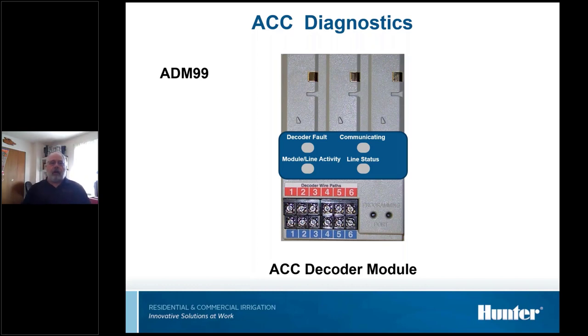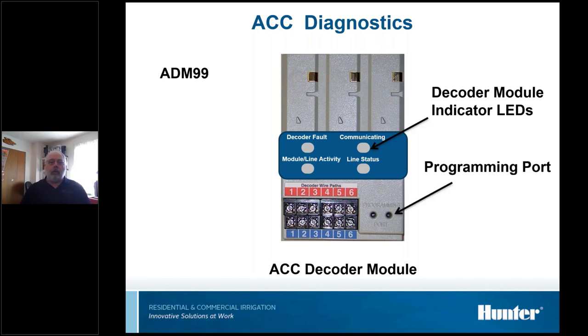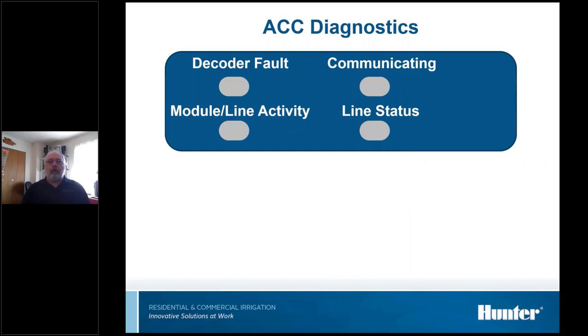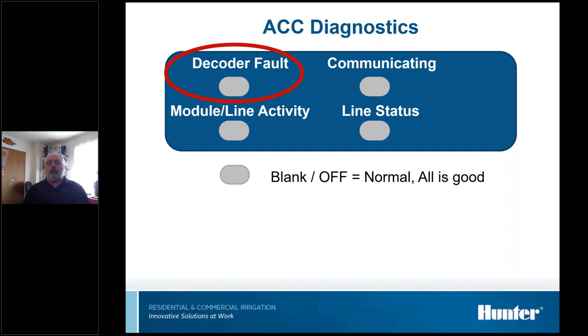So as far as diagnostics, the ACC decoder module, the ADM99, has four LED lights to tell us what's going on, and a programming port. Here's how the lights work. The thing I'll tell you right away, and you'll see it at the end, is that green is good. That's what we're always looking for. When I walk up to an ACC controller, I open it up, and I want to see the green line status light. The decoder fault light, normal is blank. It doesn't do anything. That's what you want to see when you open one up.